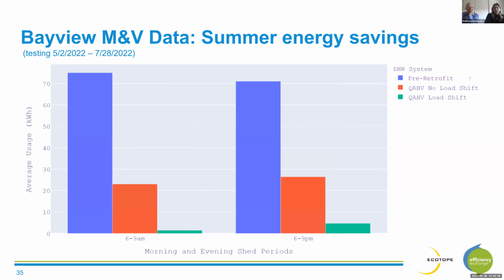And then this plot shows some similar results. We have it separated by a morning peak period and an evening peak period. Pre-retrofit, using the electric resistance system, we used around 75 kilowatt hours of energy per peak period. With the QAHV, we use significantly less energy, and then when we load shift with the QAHV, we can reduce that to just a handful of kilowatt hours per peak period.